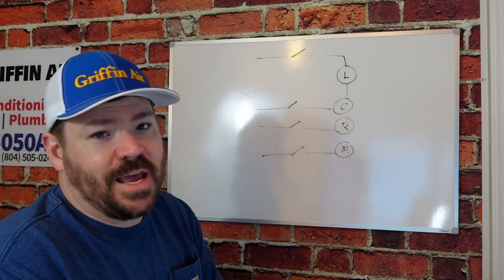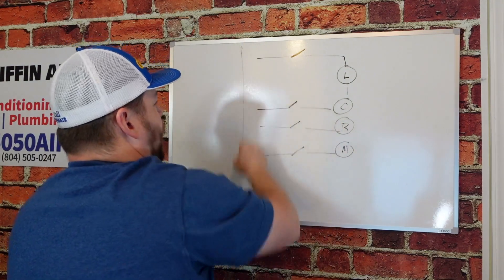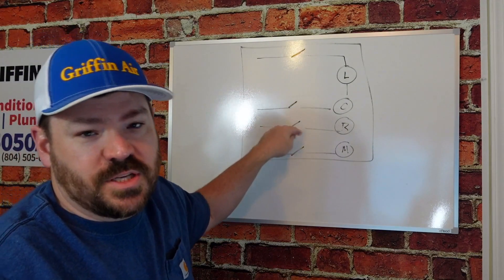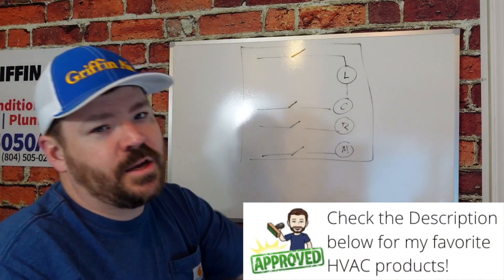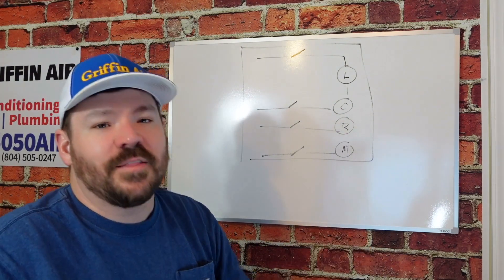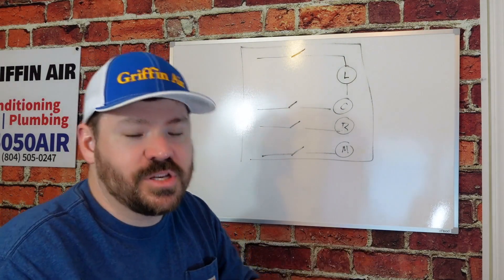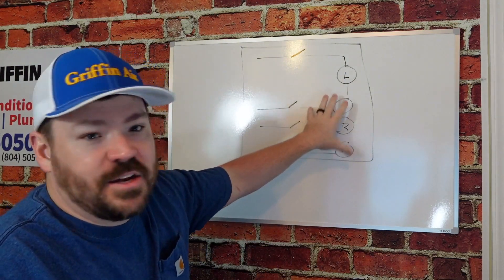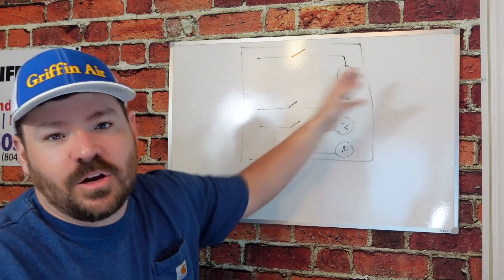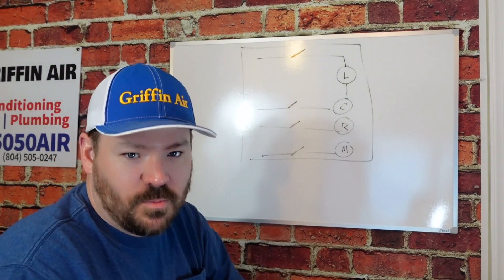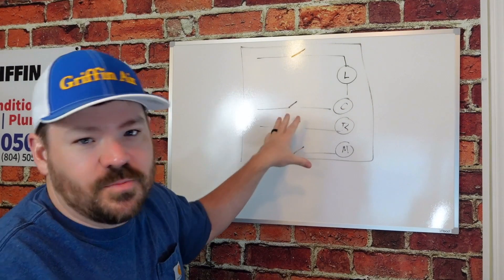That's all a non-communicating thermostat does. All a non-communicating thermostat is, is a series of switches inside. Depending on what mode you put it in and what temperature you set, it will close certain switches and open them up. That's why there are different colored wires, that's why you have to have a certain number of wires. Inside your thermostat, you have a whole bunch of switches that can close and tell things in the heating and air system: 'I need you to close now, I need you to turn on.' So on a basic level, that's a non-communicating thermostat.